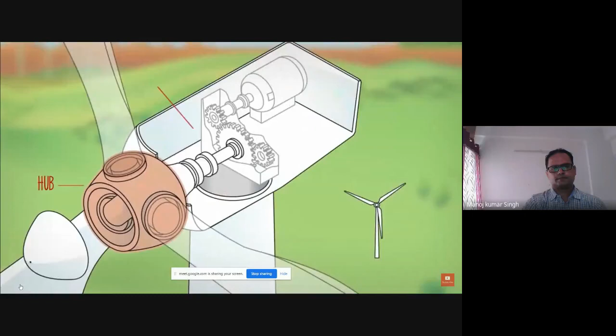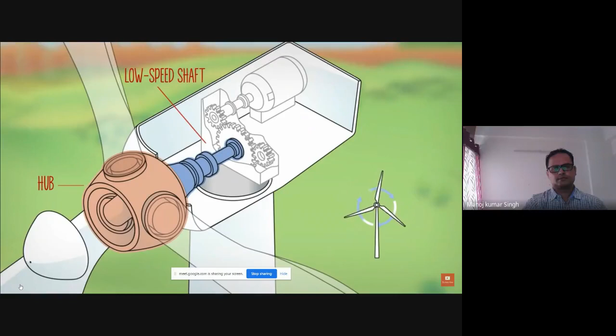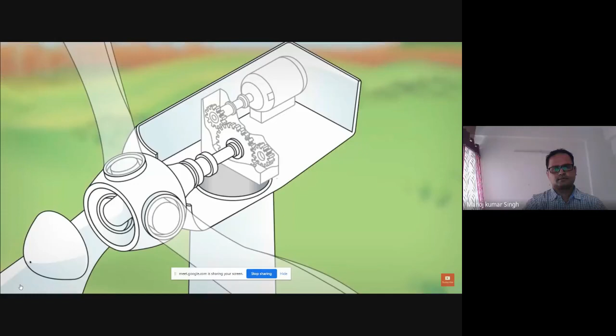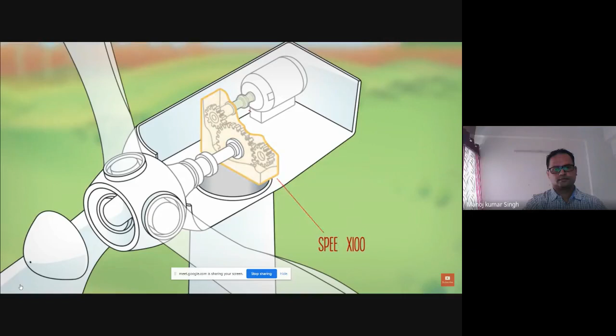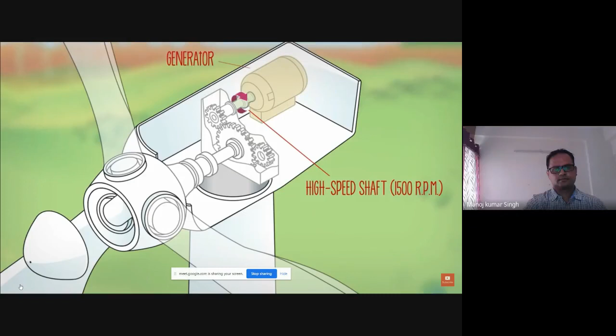The blades are attached to the wind turbine through the hub, which is coupled to the low-speed shaft. The low-speed shaft spins at the same speed as the blades, between 7 and 12 revolutions per minute. To produce electricity, it is necessary to increase the turning speed, which is the mission of the gearbox, raising the speed over 100 times and transferring it to the high-speed shaft, which rotates at up to 1500 revolutions per minute and is connected to a generator.